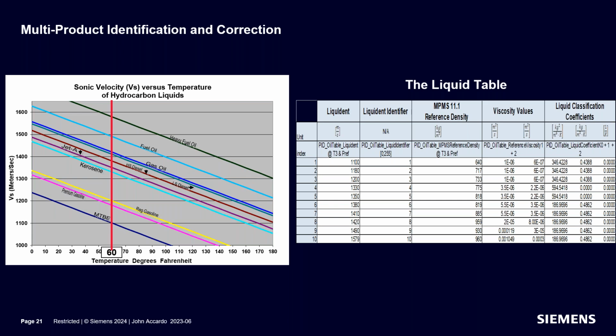It's a little bit different than the 1010 version in some ways. It's identical in every way except that there's no product names. There's just identifiers. But what you see in the left column here are speeds of sound. But they're not called speed of sound. They're called liquident. And that's because it's a speed of sound corrected to 60 degrees Fahrenheit.